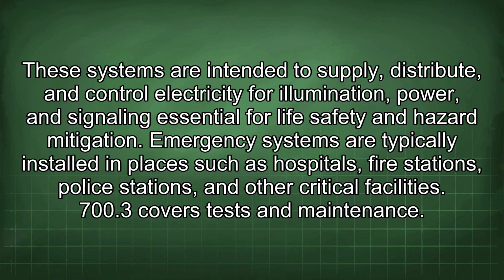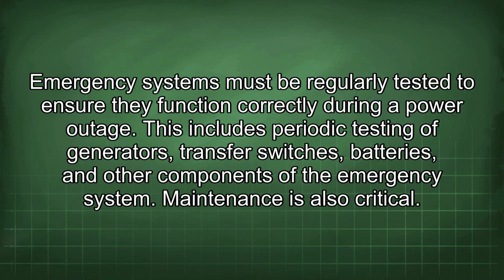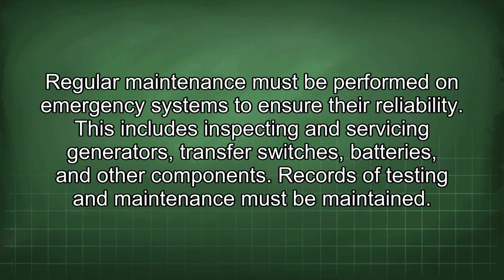700.3 covers tests and maintenance. Emergency systems must be regularly tested to ensure they function correctly during a power outage. This includes periodic testing of generators, transfer switches, batteries, and other components of the emergency system. Maintenance is also critical. Regular maintenance must be performed on emergency systems to ensure their reliability. This includes inspecting and servicing generators, transfer switches, batteries, and other components.